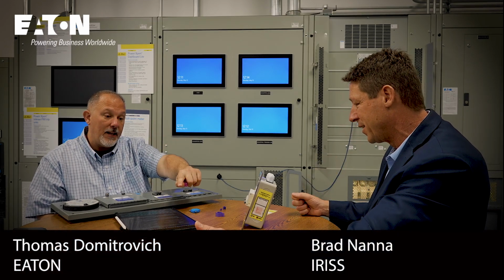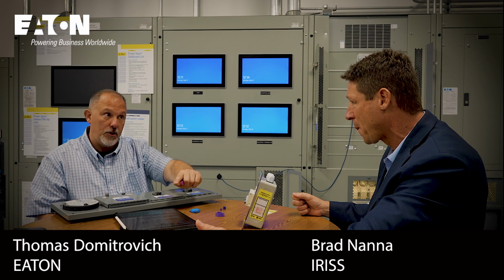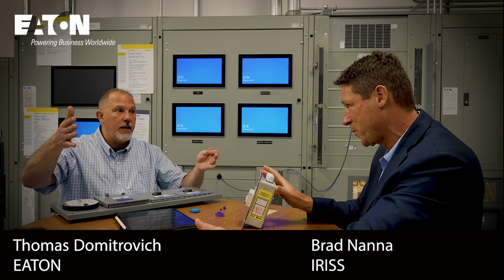What this tells you is that you don't have to wait until then - there are other indicators that mean you may need to pull maintenance sooner. This could be an indicator that something is heating up within the wires or the bus bar, because we have one for bus bars as well that goes on the bus bar.